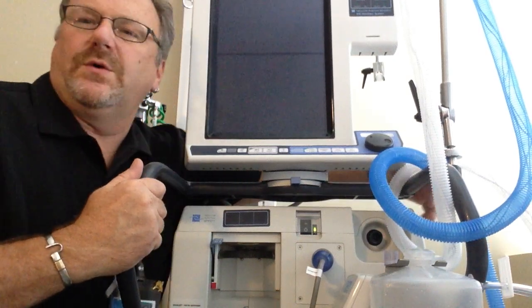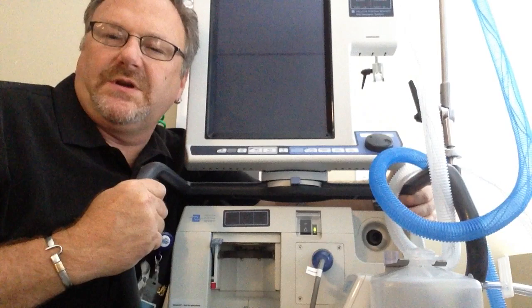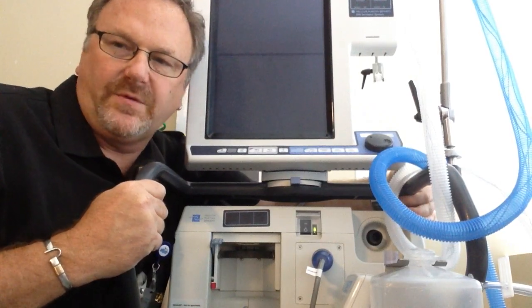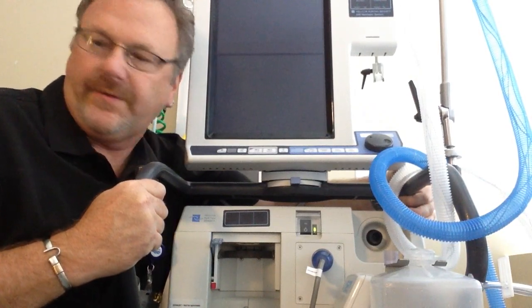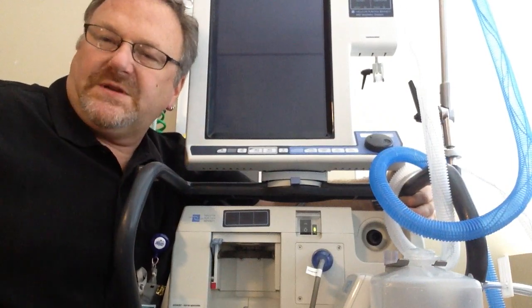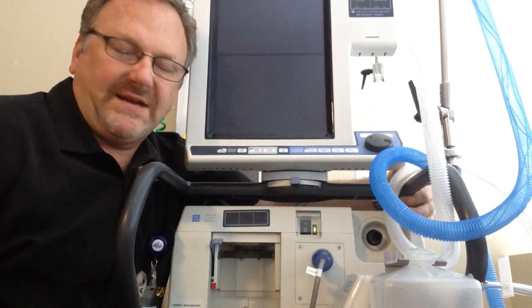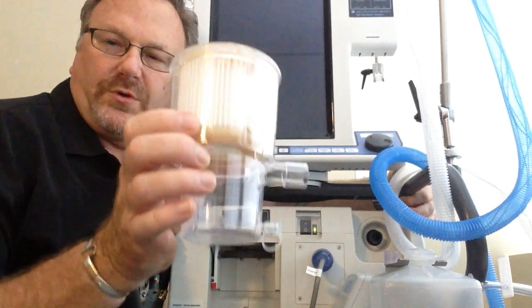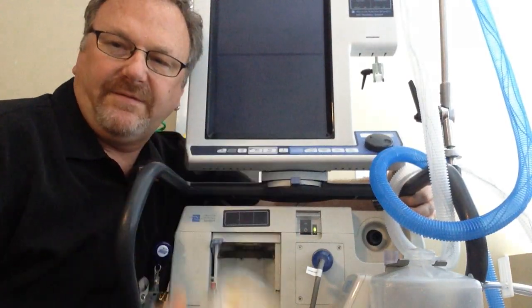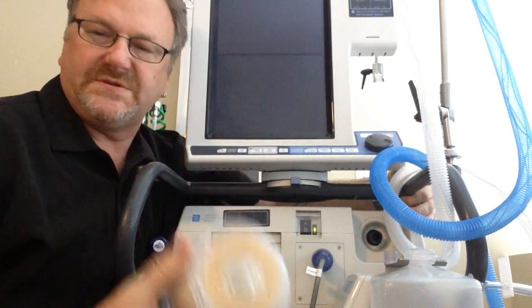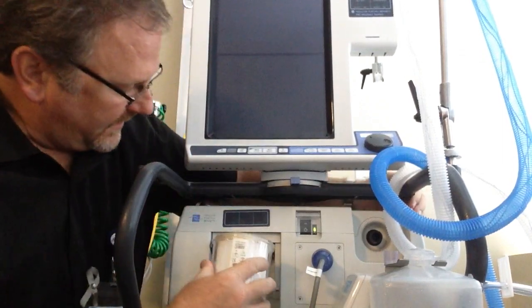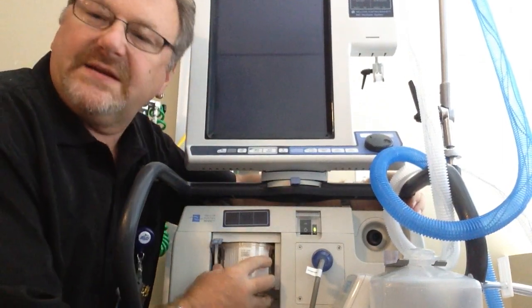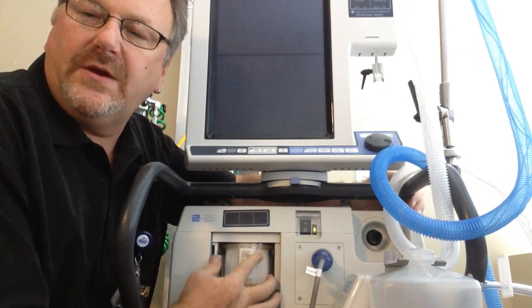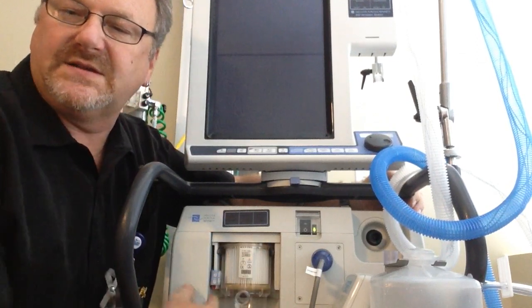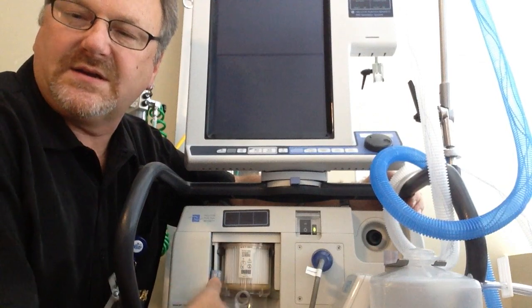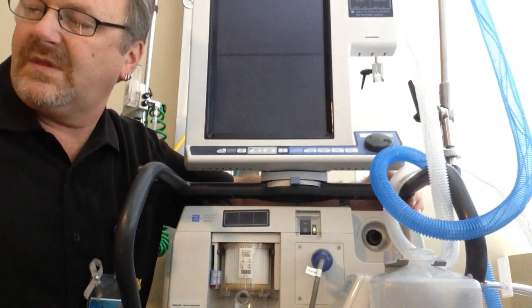This video is going to show you how to put the circuit on and do the pre-use test for the Puritan Bennett 840 ventilator. The first thing we want to do is put our filters in line. This is the expiratory filter for the Puritan Bennett 840. It is made specifically for this ventilator. It slides into a little track here, and then you push the lever down and that locks it in place. Up is unlocked, down is locked.